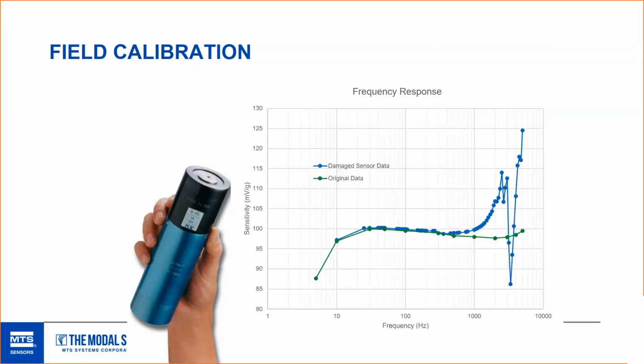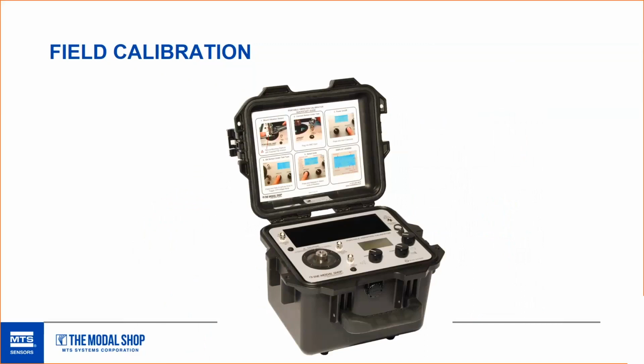But what if you have a damaged sensor, like we talked about before, a debonded element, or it was dropped and there's crystal damage? With your field calibrator only providing a fixed amplitude and a fixed frequency, are you going to be able to test for a damaged sensor every time? Think about that in the back of your mind, not to panic everyone. I don't want everyone to run from this presentation screaming that they're doing all the wrong things. But think about other options. Other devices may exist that provide additional functionality.